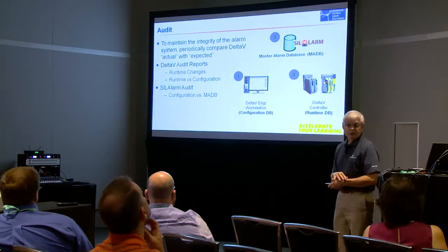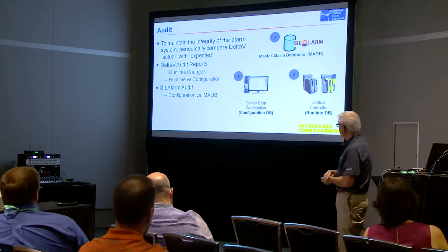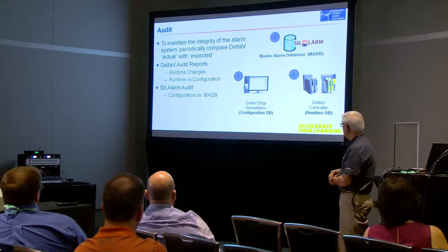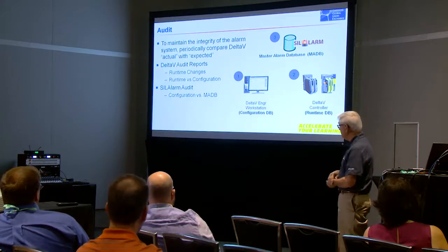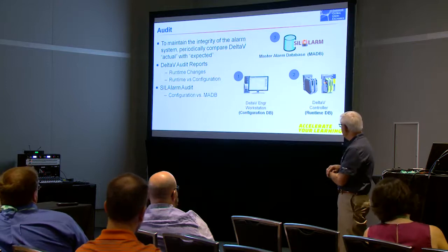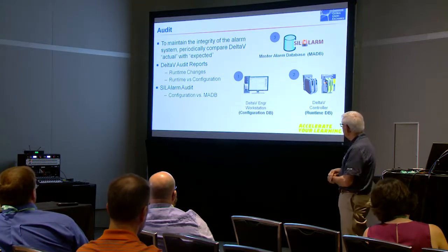This brings me to the subject of auditing. When you're auditing your alarms, of course the goal there is to make sure that what's happening in the running system is consistent with what your engineering database indicates the alarm setting should be, and of course with what the master alarm database requirements are. And so we have in Delta V two audit reporting mechanisms.